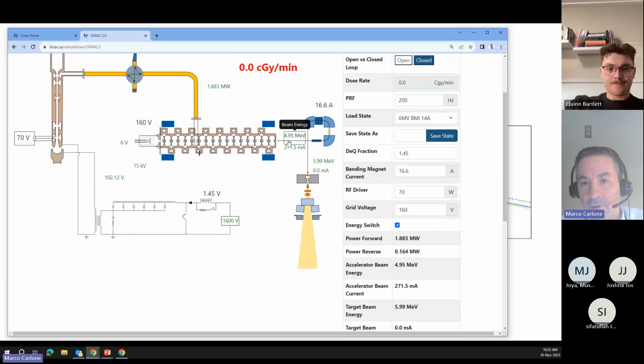So I knew ahead of time how to set this up, because I calculated this before. I knew that when I reduced the bending magnet current to 14, it was going to reduce the electron beam energy, and so I had to change the grid voltage on the gun in order to compensate for that. So now I've reset that, and if we go to our treatment head screen, we see that we have a new profile that we've created for this.